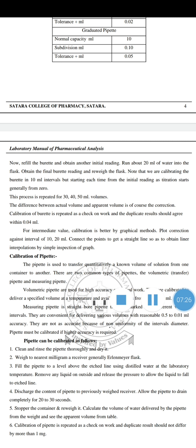Then calibration of the burette is repeated as a check on work, and the duplicate result should agree within 0.04 ml. For intermediate values, calibration is better done by graphical methods. Plot correction against intervals of 10-20 ml, then connect the points to get a straight line so as to obtain linear interpolations by simple inspection of the graph. Then this is the calibration of a burette.